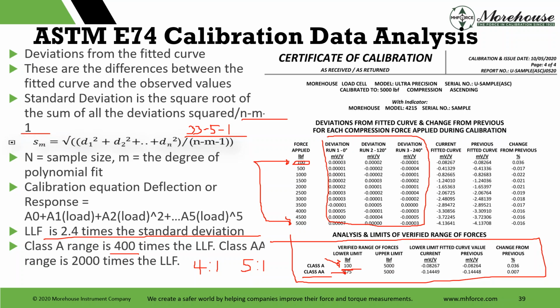In addition to that, we start looking at change from previous on the data. On this data set, that's another thing that you want to consider when you do your uncertainty. You want to consider the stability. Lots of ways to do this. You can use just one set of data, this would be type B, or you can use multiple types of data. One calibration to the next is typically what we see a lot of people plug these numbers in.